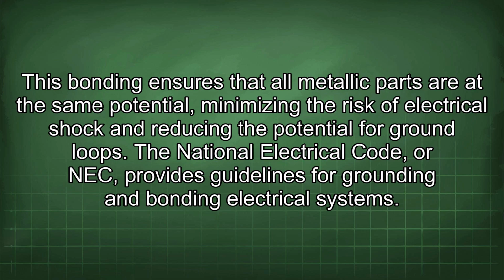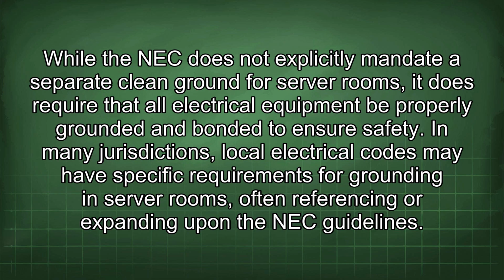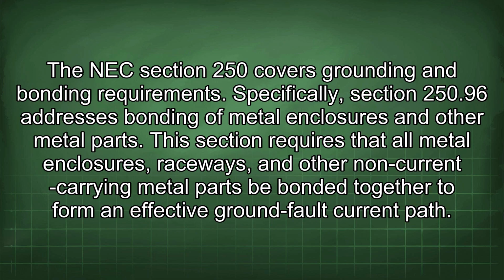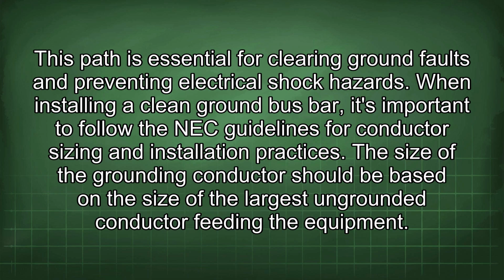The National Electrical Code, or NEC, provides guidelines for grounding and bonding electrical systems. While the NEC does not explicitly mandate a separate clean ground for server rooms, it does require that all electrical equipment be properly grounded and bonded to ensure safety. In many jurisdictions, local electrical codes may have specific requirements for grounding in server rooms, often referencing or expanding upon the NEC guidelines. The NEC Section 250 covers grounding and bonding requirements. Specifically, Section 250.96 addresses bonding of metal enclosures and other metal parts. This section requires that all metal enclosures, raceways, and other non-current carrying metal parts be bonded together to form an effective ground fault current path. This path is essential for clearing ground faults and preventing electrical shock hazards.